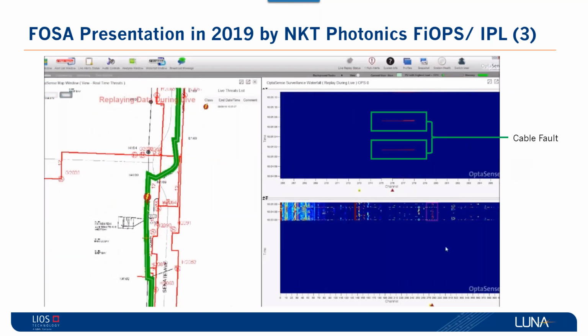One of the advantages of the same fiber optic that was installed is that they also showed they can do cable fault location and fault detection as well. What was presented at the time, and what we hope to do in the next webinar, is to show how you can also use DAS for, I will not say partial discharge monitoring, because that is not true. There are certain things you can do, but detecting different anomalies in joints.